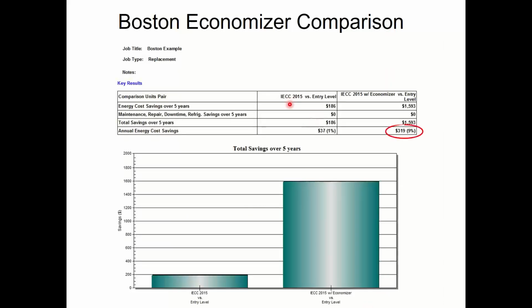Just going from that basic unit to the code compliant unit was, in this project example, whatever example I picked, I think it was an 8 or 10 ton rooftop unit for an office, a $37 savings, 1%. Adding the economizer was another 8%. An economizer will save significantly more than going to a high efficiency unit. High efficiency units are not that exciting in the grand scheme of things.